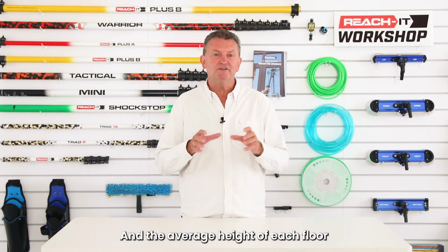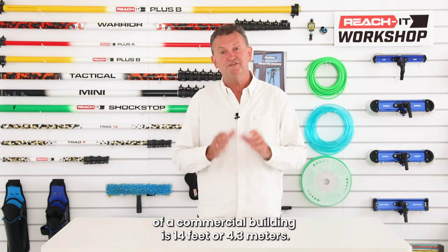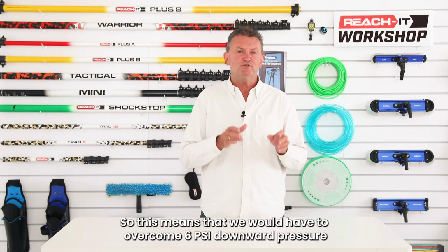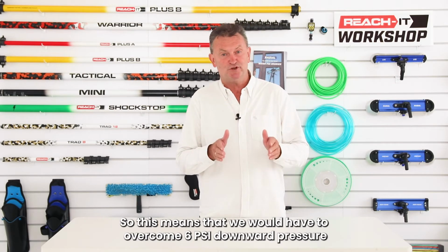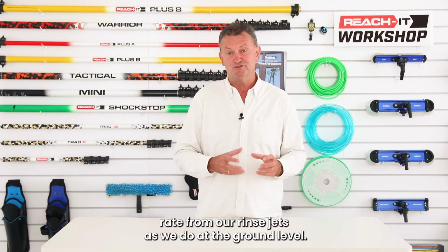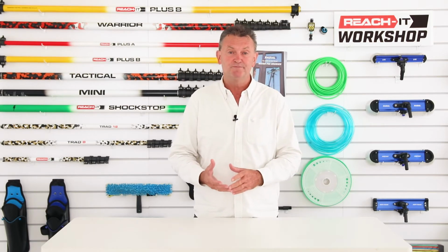And the average height of each floor of a commercial building is 14 feet or 4.3 meters. So this means that we would have to overcome 6 psi downward pressure per floor we go up to have the same flow rate from our rinse jets as we do at the ground level.